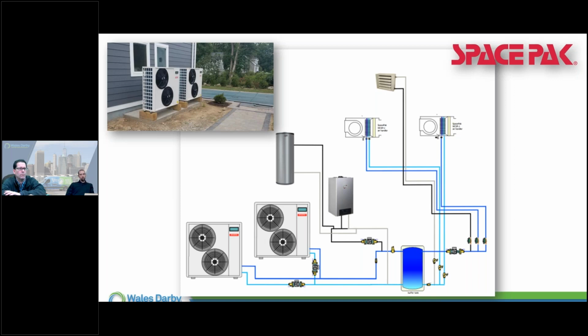Maybe that boiler will kick on and lend a hand to get that buffer tank up to temperature. So we can be creative. We had an application not too long ago with a contractor who was almost ready to walk away, saying it's not going to work. But we don't always have to remove the fossil fuel device. If they have a new boiler that was replaced 5, 6, 7, maybe 10 years ago, maybe we don't have to get rid of it. Maybe we just size the outdoor unit for a majority of the load and let the boiler take over on those colder days, so these pieces of equipment work in conjunction with each other instead of sizing the entire job off the heat pump.